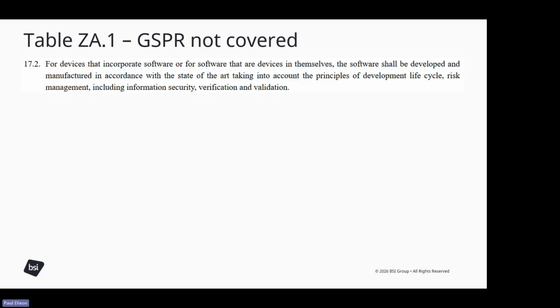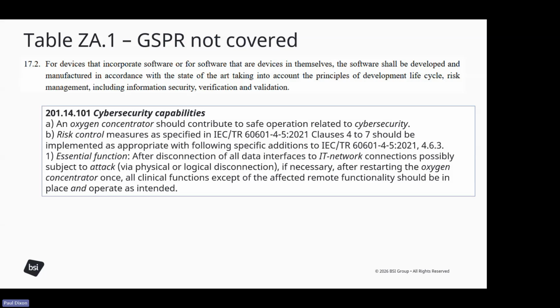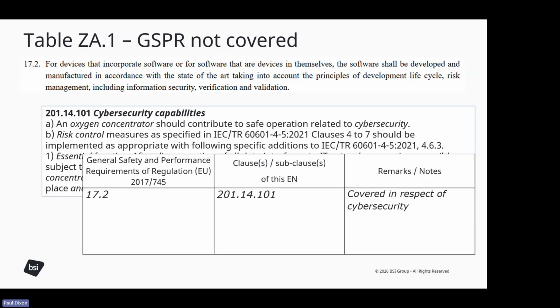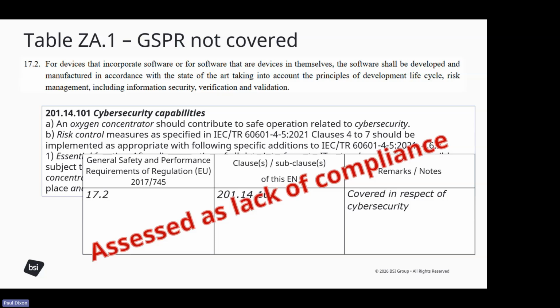Another example, GSPR 17.2 about software development life cycles and risk management. We have a clause in the oxygen concentrator standard that says an oxygen concentrator should, and risk control measures should. Shoulds are not normative. So even though we initially tried to claim coverage, that was assessed as lack of compliance. You can't take credit for a clause that doesn't include the word shall.